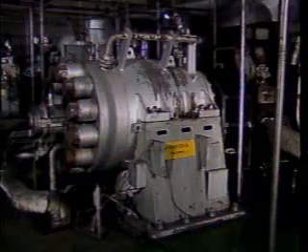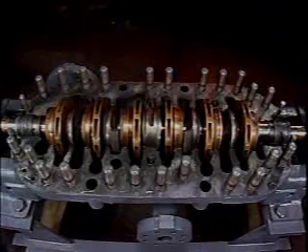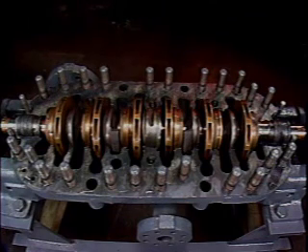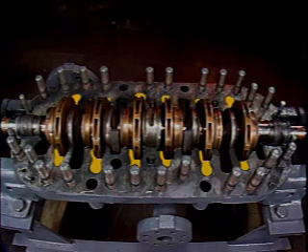out of the tank. All centrifugal pumps work by creating a centrifugal force. This force moves the liquid through the pump and increases the liquid's pressure. In applications where large increases in pressure are needed, multi-stage centrifugal pumps are often used. A multi-stage centrifugal pump contains 2 or more impellers and volutes in a single casing.